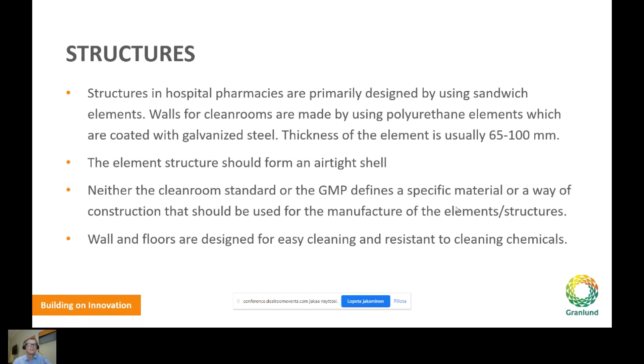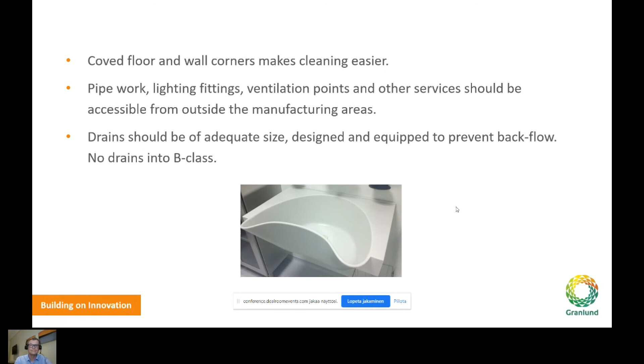Coved floor and wall corners make cleaning easier. Pipework, lighting fittings, ventilation points and other services should be accessible from outside of the clean room areas, and drains should be of adequate size, designed and equipped to prevent backflow. And in B-class areas there can't be any drains. Horizontal surfaces where dust can accumulate are tried to be avoided.